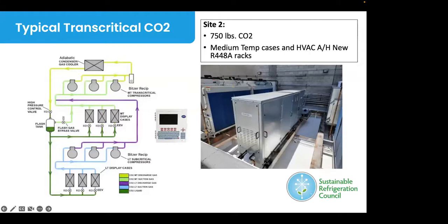Site number 2, again, this was a store where the medium temp cases were not being replaced either. So in this particular system, we came in again with a cascade system, R448A over a transcritical CO2 system at this store. The transcritical CO2 picked up all of the low temp. At the same time, since the cases weren't being replaced for merchandising purposes, we still went ahead and picked up all of the medium temp evaporators in the walk-in cooler.